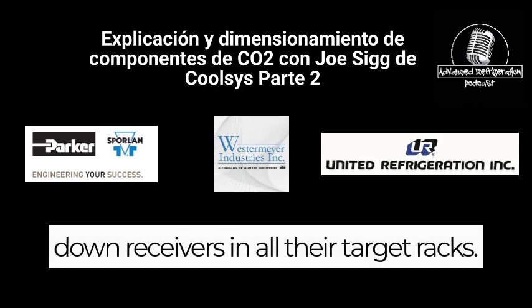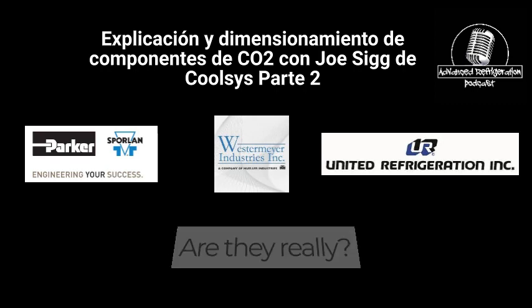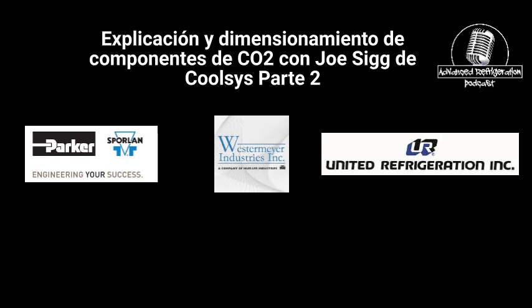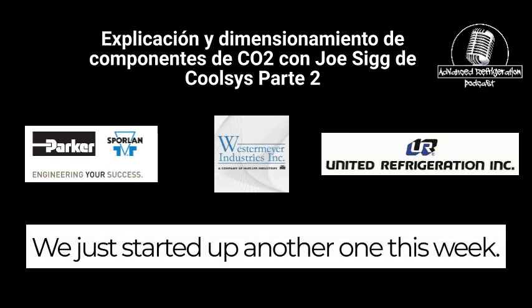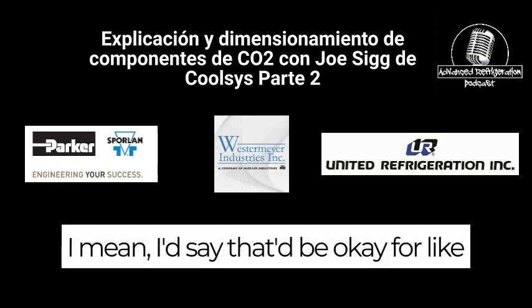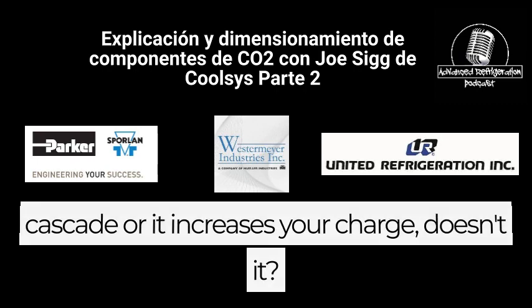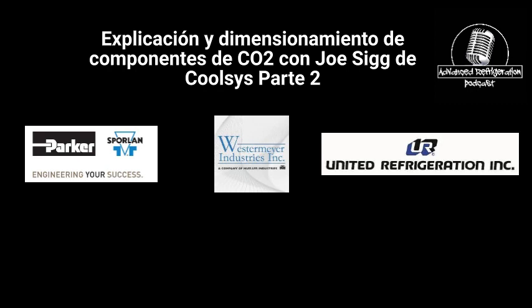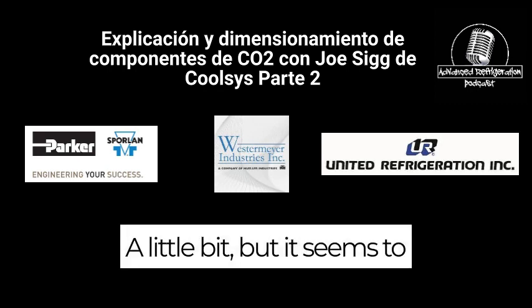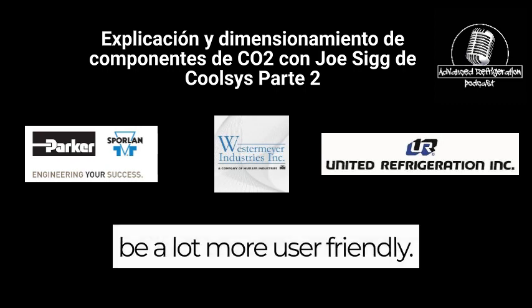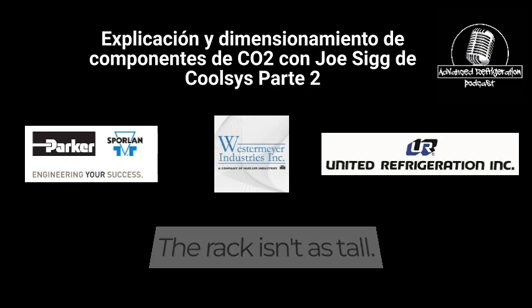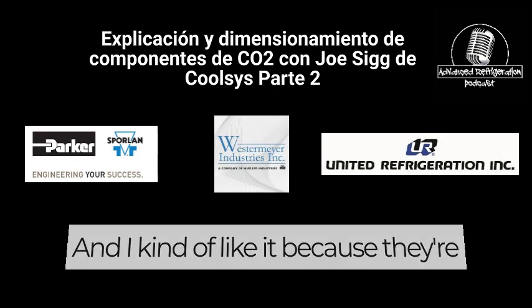It's funny, because Zero Zone is installing laid-down receivers in all their target racks. Are they really? We just started up another one this week. I'd say that'd be okay for Cascade. It increases your charge, doesn't it? A little bit, but it seems to be a lot more user friendly. The rack isn't as tall, and I kind of like it.